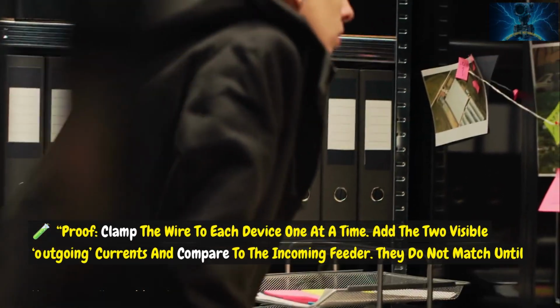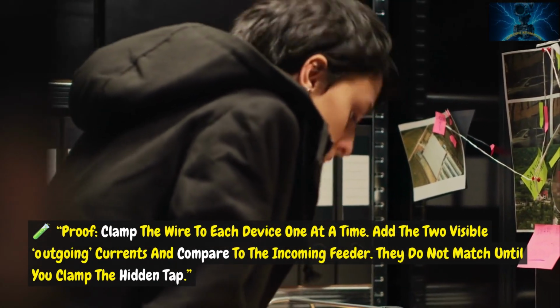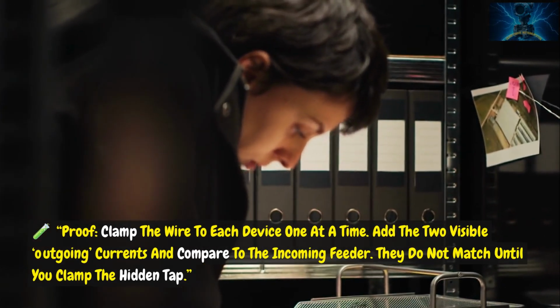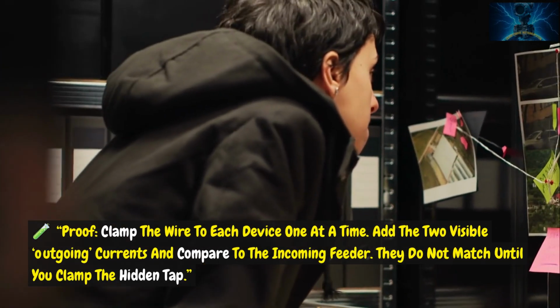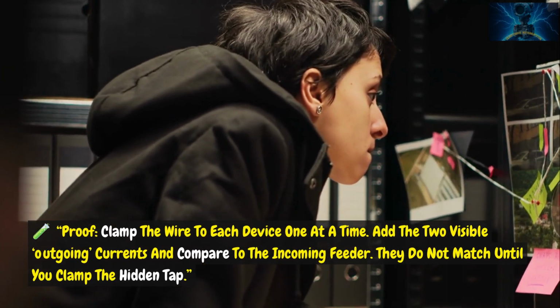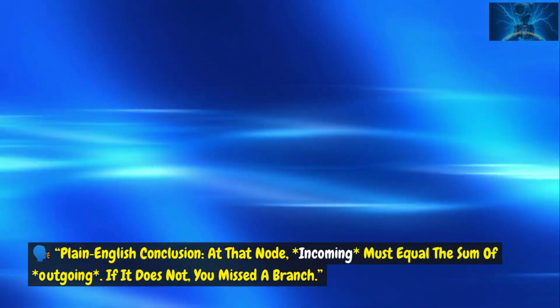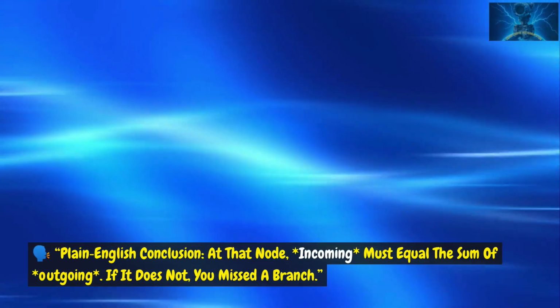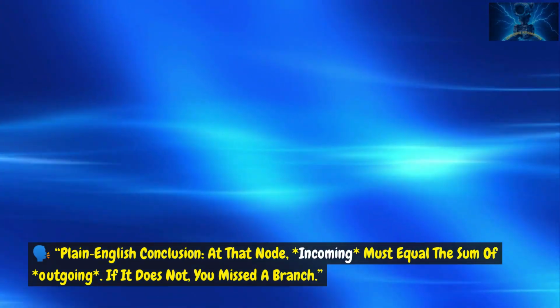Proof. Clamp the wire to each device one at a time. Add the 2 visible outgoing currents and compare to the incoming feeder. They do not match until you clamp the hidden tap. Plain English conclusion. At that node, incoming must equal the sum of outgoing. If it does not, you missed a branch.